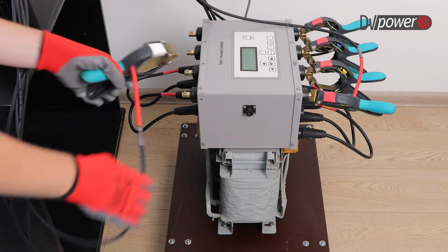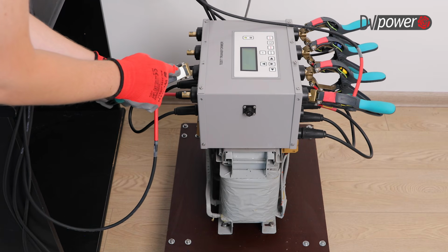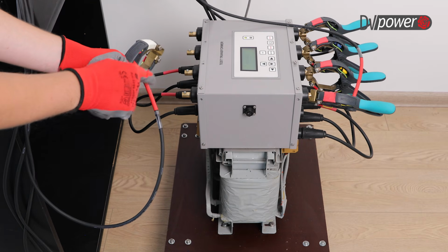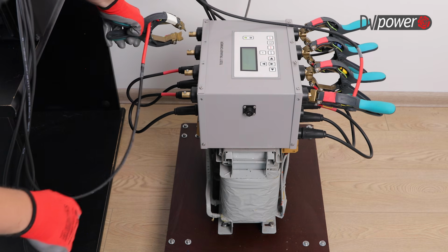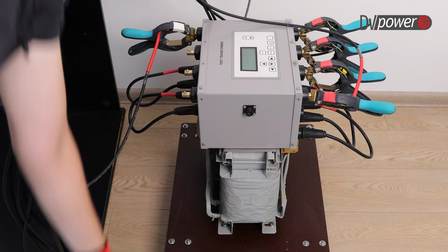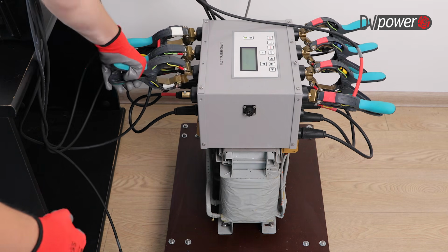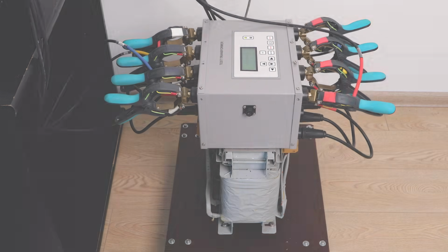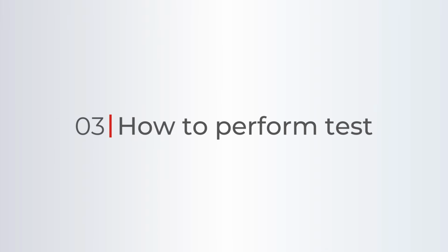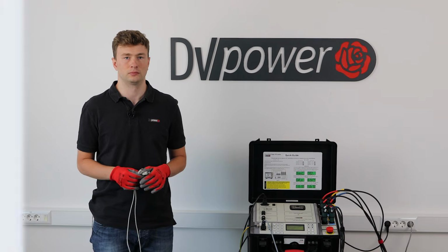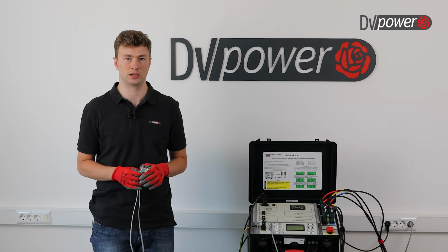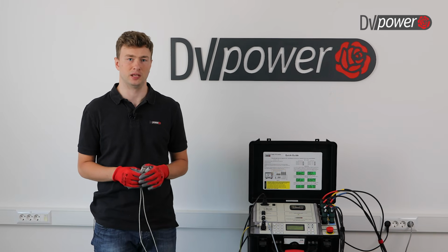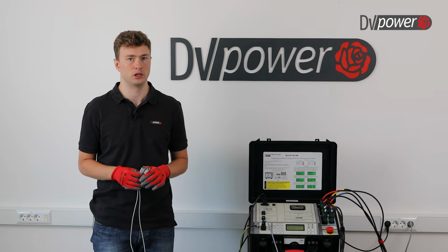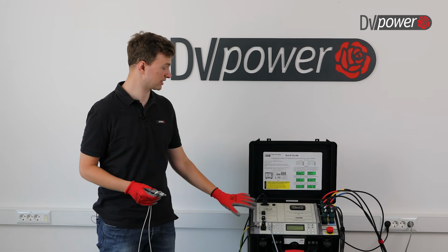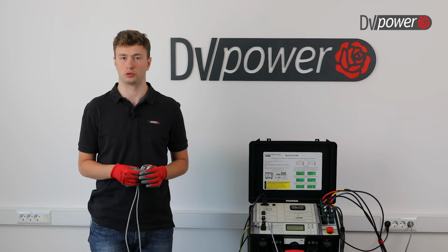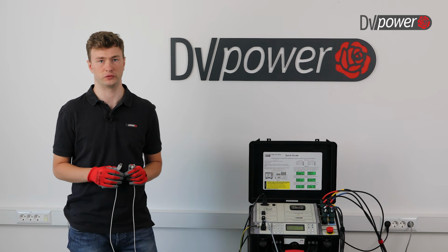On the low voltage side, we have a white label. Again, we follow color patterns and connect the red one to phase A. The device is ready, it's running, and it's connected to the transformer. Now we have two solutions for testing, whether we want to use the device in a standalone mode or we want to control the device using our PC software.